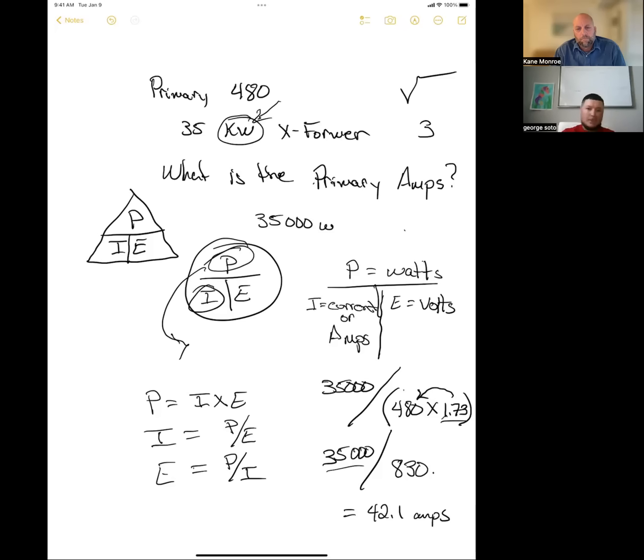35,000 divided by 480 times 1.732. Yep. And then we divide 35,000 by 830. Yep. Okay. And that right there is your amperage on your primary side. Okay.